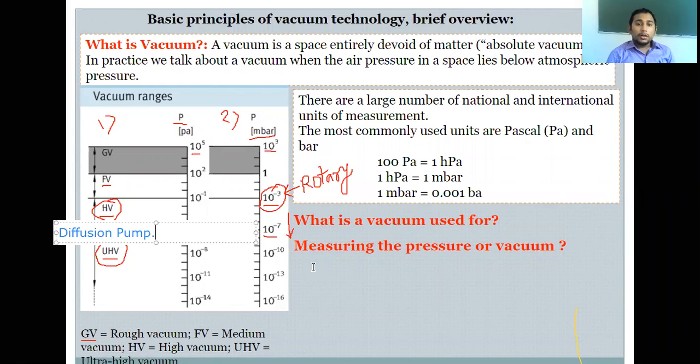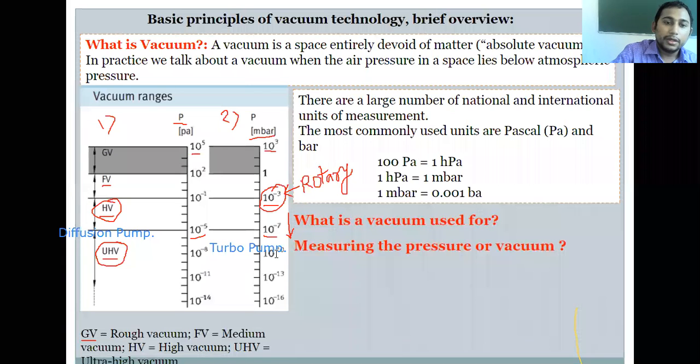If we need to create a vacuum or pressure of 10 raised to minus 10 millibar, or less, inside the chamber, then a turbo pump is required.